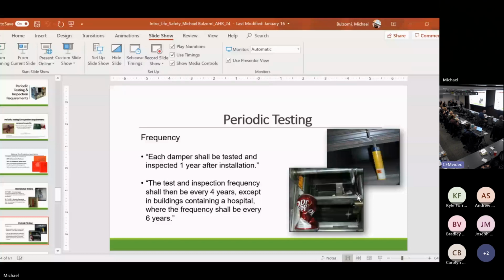You open it, and more than likely this is a construction issue. I've got a bunch of contractors that have no power to the damper. They're hot, they've got air, but they've got no power to the damper. So what do they do? They slip the jack shaft, prop something in it, and get their air to their site. Then they're done working and finish everything they do. They forgot they did this to the damper. Well, if I didn't have the commissioning, the 1 year and then every 4 year testing, I'd never catch this. And 85 people would die in the MGM Grand Hotel fire every year. But because we have this, it's supposed to catch any of these deficiencies that happen during construction or remodel or tenant movement.